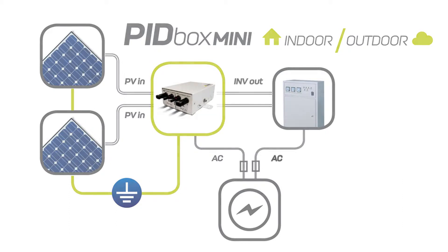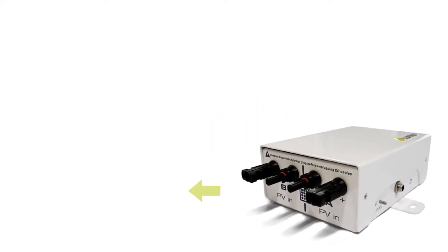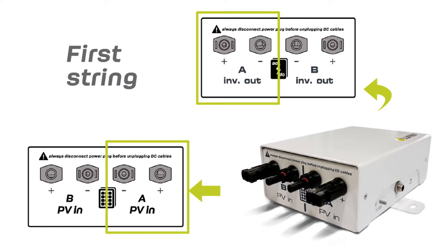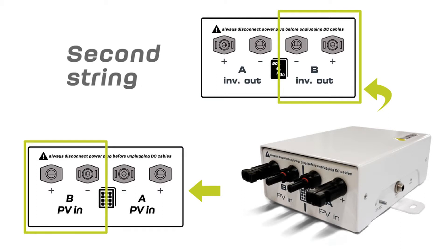The PID Box Mini has two connections on the PV in side and on the INV out side, A and B. This way, you can connect a second string of solar panels which is independent, for example, a second MPPT.